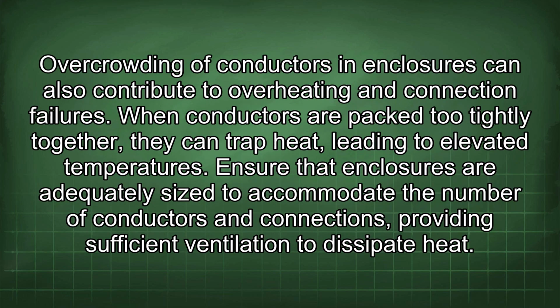Overcrowding of conductors in enclosures can also contribute to overheating and connection failures. When conductors are packed too tightly together, they can trap heat, leading to elevated temperatures. Ensure that enclosures are adequately sized to accommodate the number of conductors and connections, providing sufficient ventilation to dissipate heat.